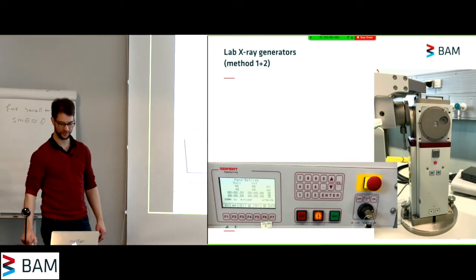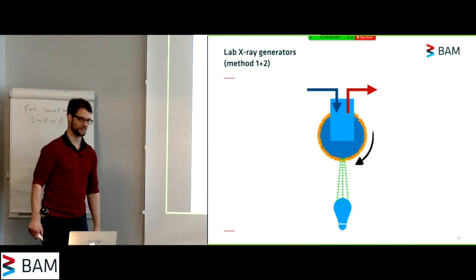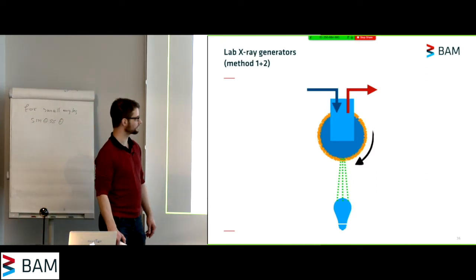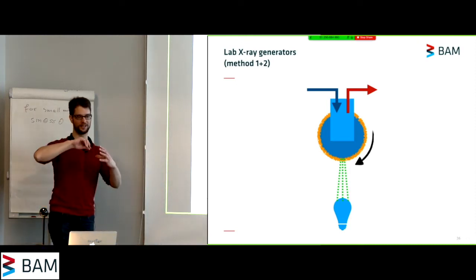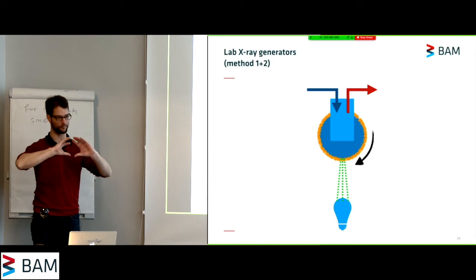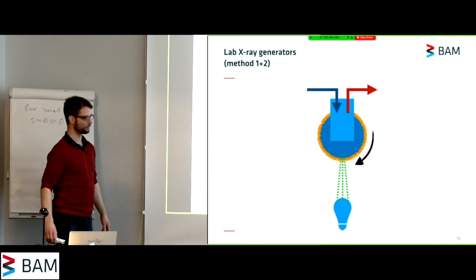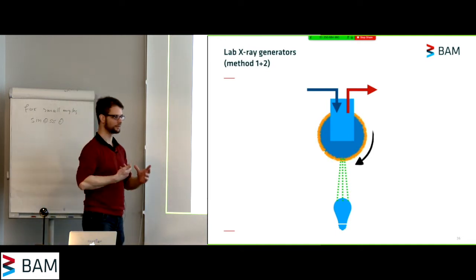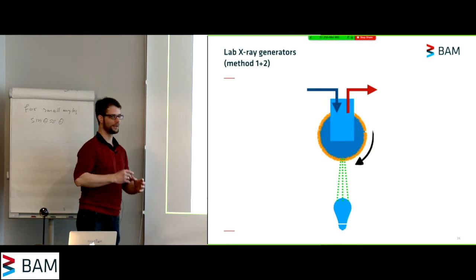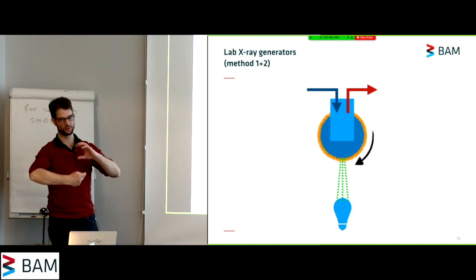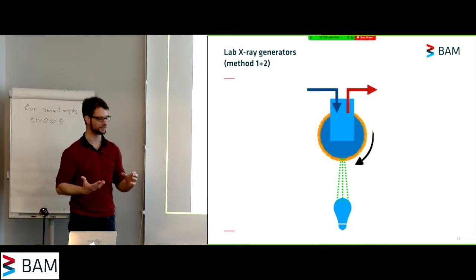So people came up with different ideas. One of which was the rotating anode X-ray generator. These are a bit more expensive. But what they do is they spread out the heat load over the surface of a drum. So they're spinning around a drum with a target coating on it, either copper or molybdenum or whatever energy you need. And by spinning around this drum, you distribute the heat over the entire surface of the drum. And you can then cool it more efficiently.